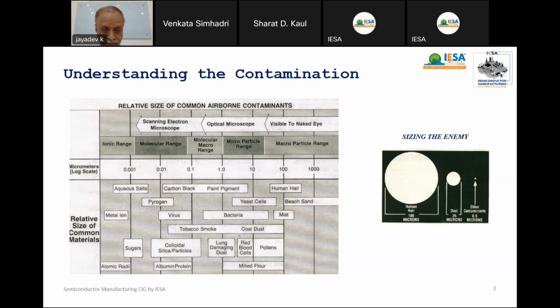Apart from that, the more dangerous is in an industrial application. Basically the process, the machinery, materials, utilities, and the people are the major sources of contamination. In the process, if we take powder residuals, soldering operations, assembly, fittings, these largely produce burrs. They are contamination. If we take machines, if it's not a clean-compatible machine, corrosion may take place, wear and tear, physical deterioration. And in the process, a lot of chemicals, acids, alkalis, solvents, particularly airborne molecular contamination, normally from wet benches, may get caught in the recirculation of the air. That may have a lot of effect through vapors. And utilities like gas piping, fittings, liquids are also sources of contaminants.